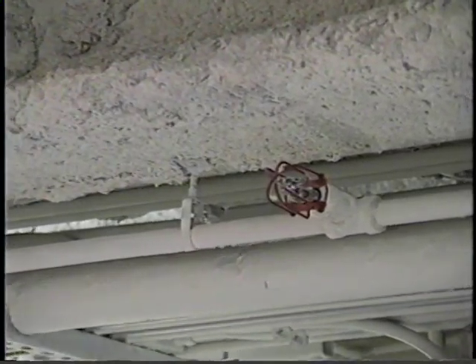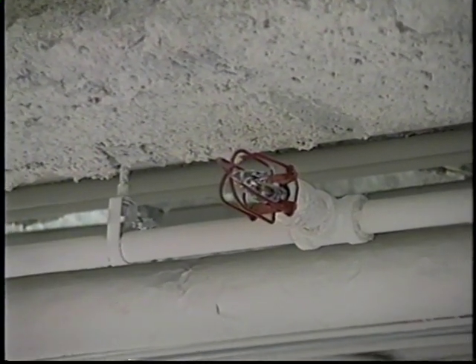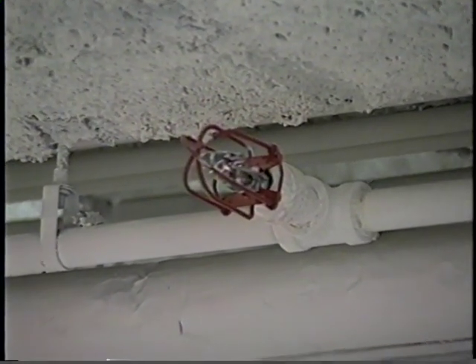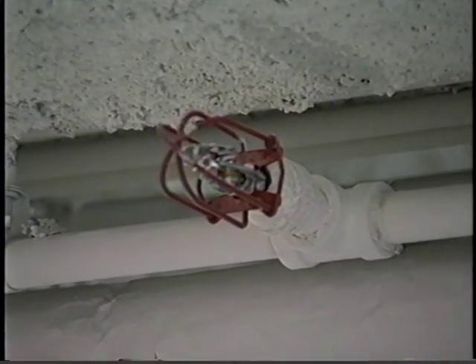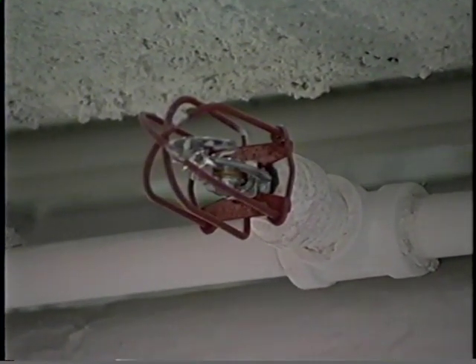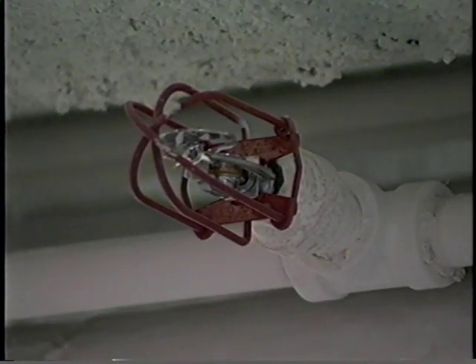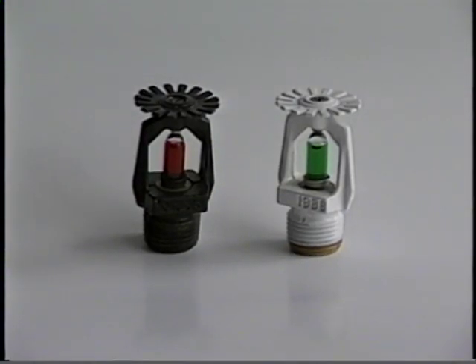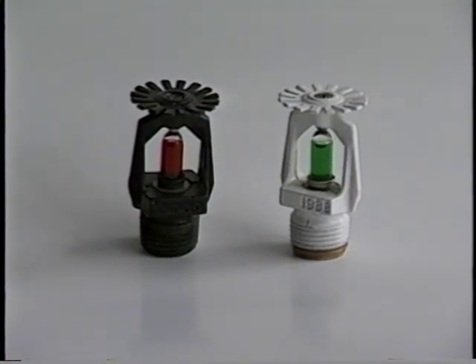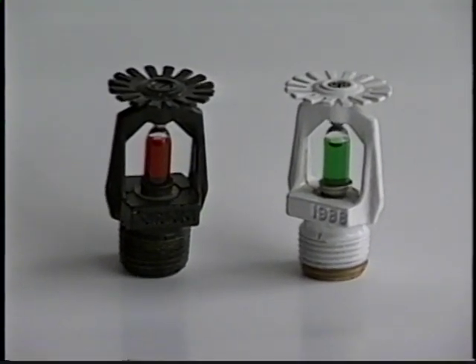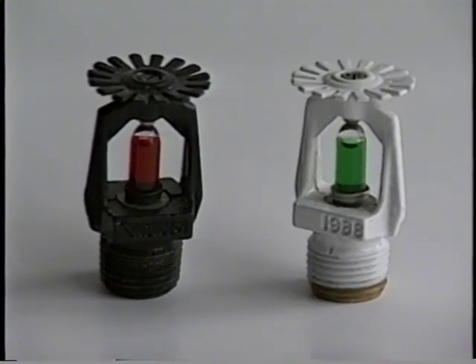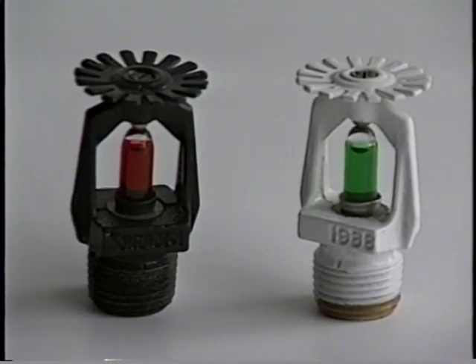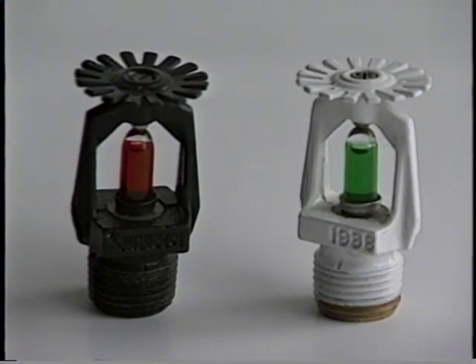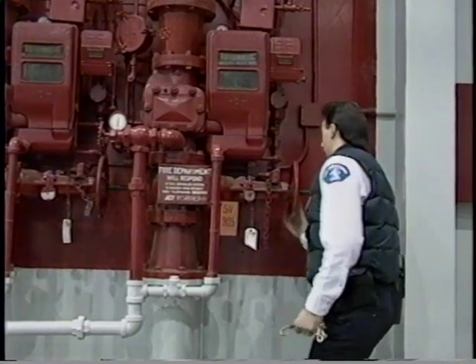The sidewall sprinkler extends from the side of a pipe and is used in small rooms where the branch line runs along a wall. It has a special deflector that creates a fan-shaped pattern of water. Special sprinklers with corrosive-resistant coatings should be installed in areas where moisture, chemical, or other corrosive vapors exist. Without this special coating, the operational parts of the sprinkler will corrode and may become inoperable in a very short time.